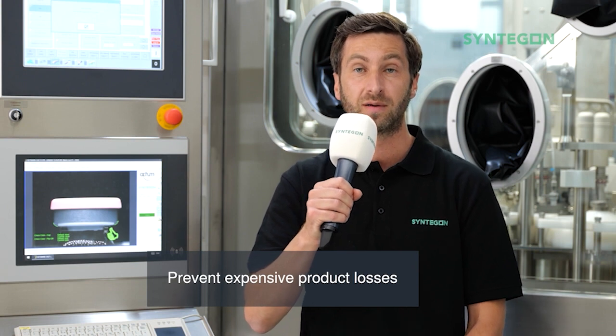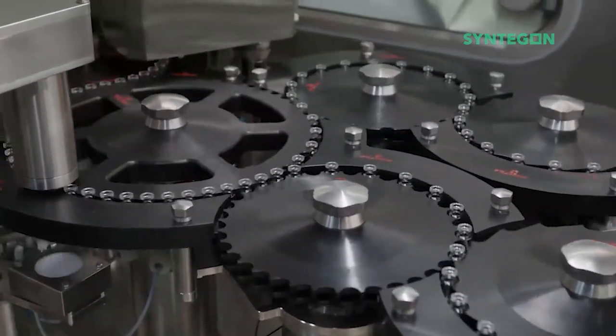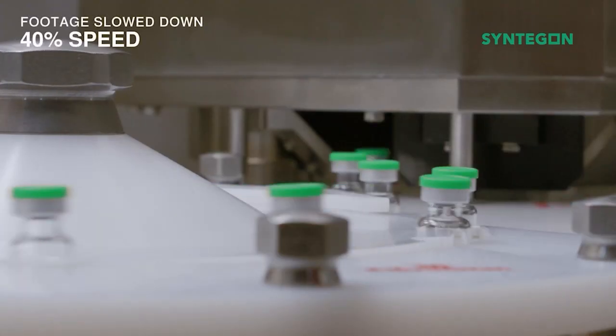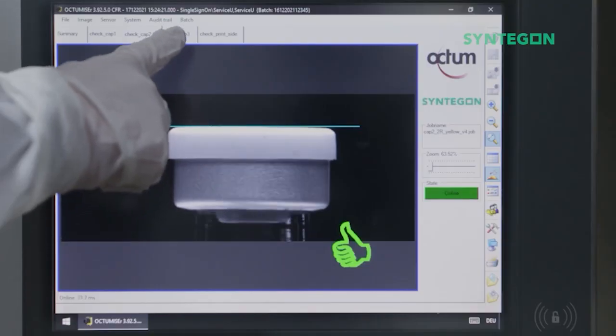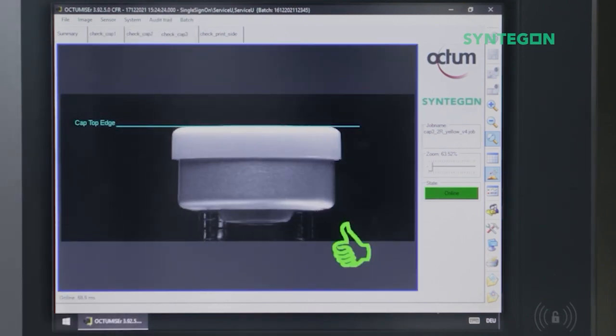Every recheck of mostly very cost-intensive products means loss of money. So what do we inspect? The first thing in a fill-finish process is that we inspect the empty vial for cosmetic defects of the bottom and of the opening. The next step is to inspect the stopper, especially the stopper gap. Then the inspection of the crimping is mandatory. The next inspection task is the cap roundness inspection, where we check for cosmetic defects and the color of the flip-off.